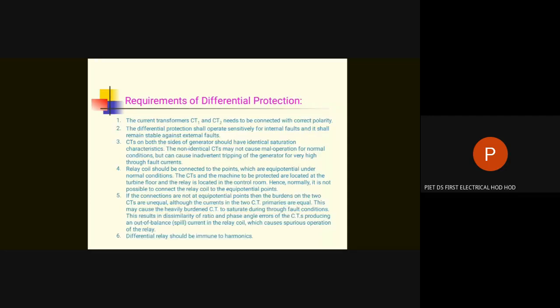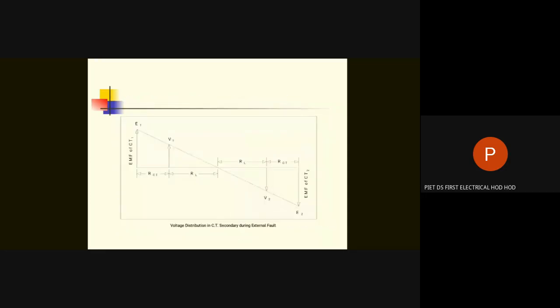What we do is this vector diagram, as it is shown: EMF of CT1 is E1, EMF of CT2 is E2. If you take out the CT secondary resistance, the terminal voltages at the CTs are V1 and V2, and if you cross these points, the point at which the relay is connected, at that point the voltage is zero, and it should be zero. But as we discussed, you cannot connect the relay exactly at the midpoint, therefore the voltage will not be zero, and mal-operation in this case has to be avoided.